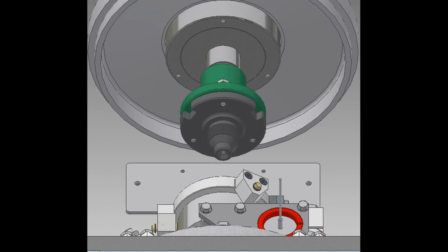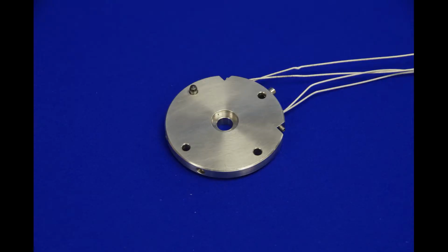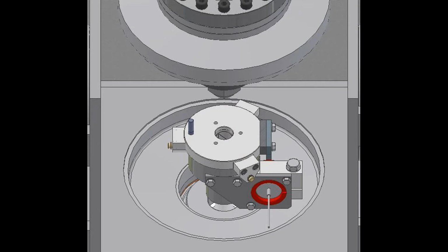Start by attaching the 4-ball upper specimen hub to the spindle flange. Fit the heater pad on top of the torque measuring assembly. Connect the heaters to the screw terminal on the back of the chamber. Connect the contact potential lead to the heater block.